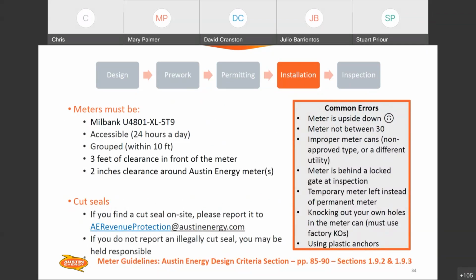So the meters must be, this is the one and only, again, it's the U4801 XL 5T9. It's a Milbank. 5T9, that T stands for terminal. So there's a way that you can see it. If you've got a meter can closed up and it's sealed, and we might have put a transparent blank in there, you can tell there's actually a 5th terminal on the center left of that socket. So if for some reason you can't get into the can, that's the clearest way visually to see that you've got that proper meter can.